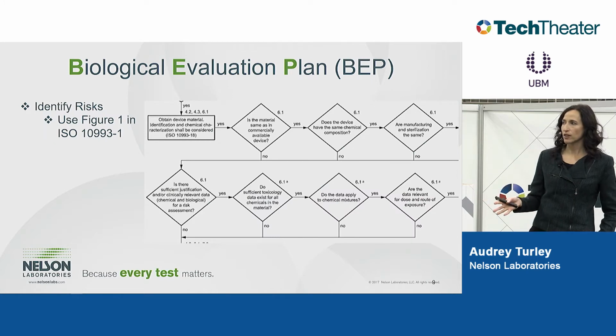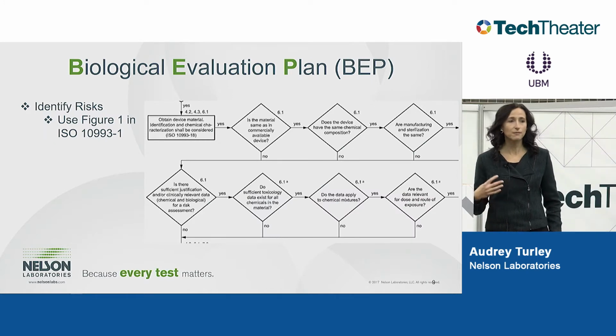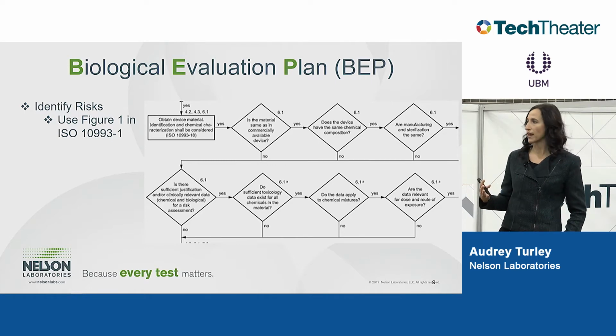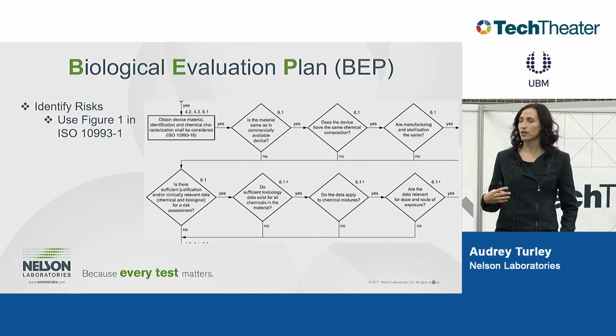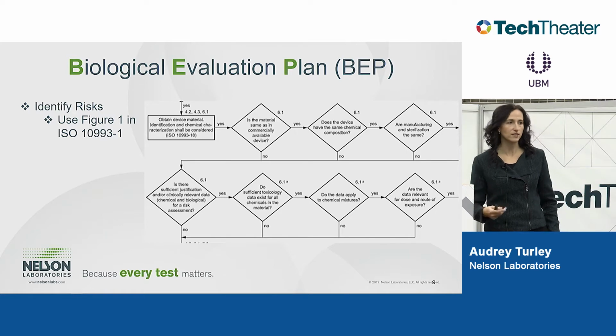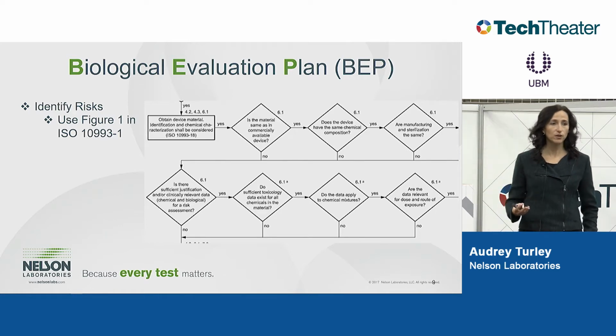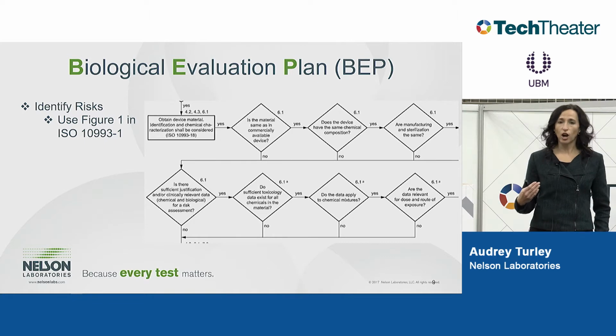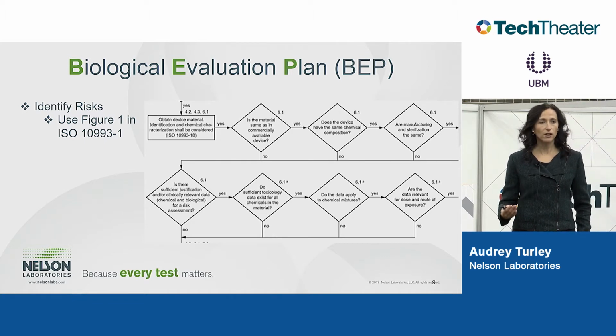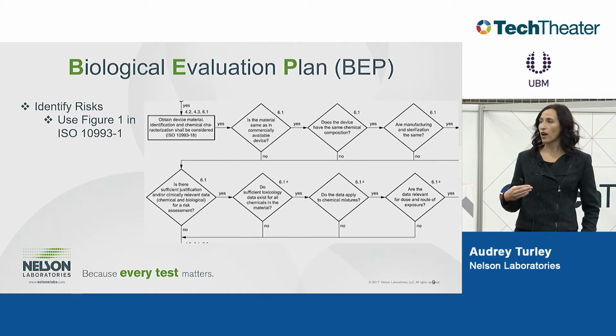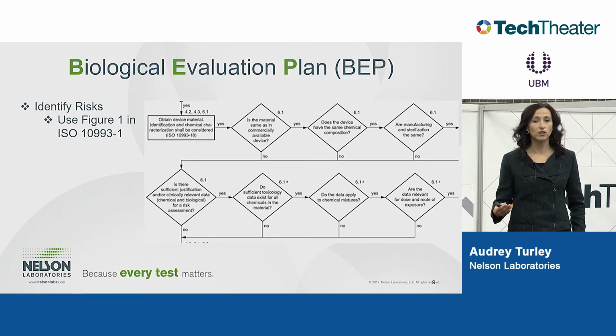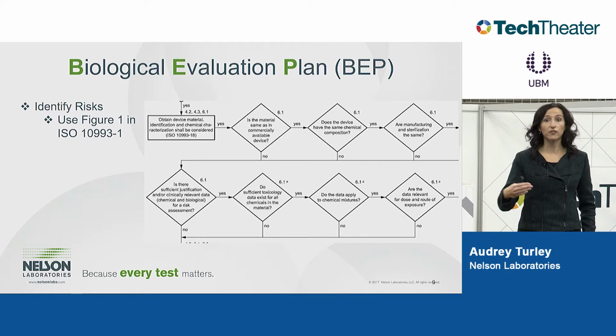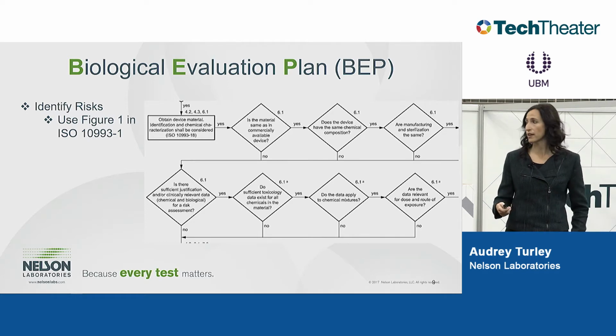So I've put up this figure. This is from ISO 10993 Part 1. This isn't meant to be read word for word right now, but it's just to let you know that there is this flow chart that gives you a thought process when you're assessing your device. So we start with materials. We start with what we already know about the device. And we can also identify if we own this material or this process in another device that's already been approved. So it's good to leverage what we already have. This could reduce your amount of testing or let you know additional testing is needed, but it will benefit you for products down the road, possibly.